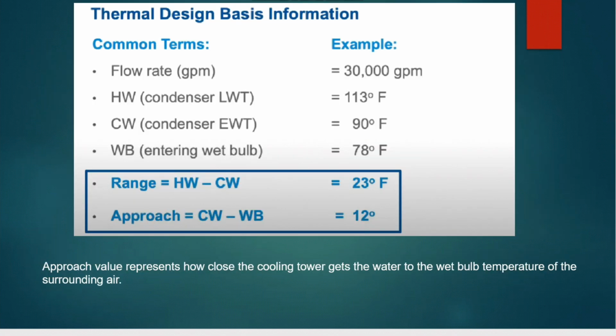So the second important thing: the range and approach. Here I have shown one example. The system flow rate, the chilled water flow rate, is 30,000 GPM, and the hot water and cold water. The hot water means the condenser leaving water temperature, so the water which comes from the chiller to the cooling tower. Here we have the cooling tower, here we have the chiller. So the water which is coming to the cooling tower.